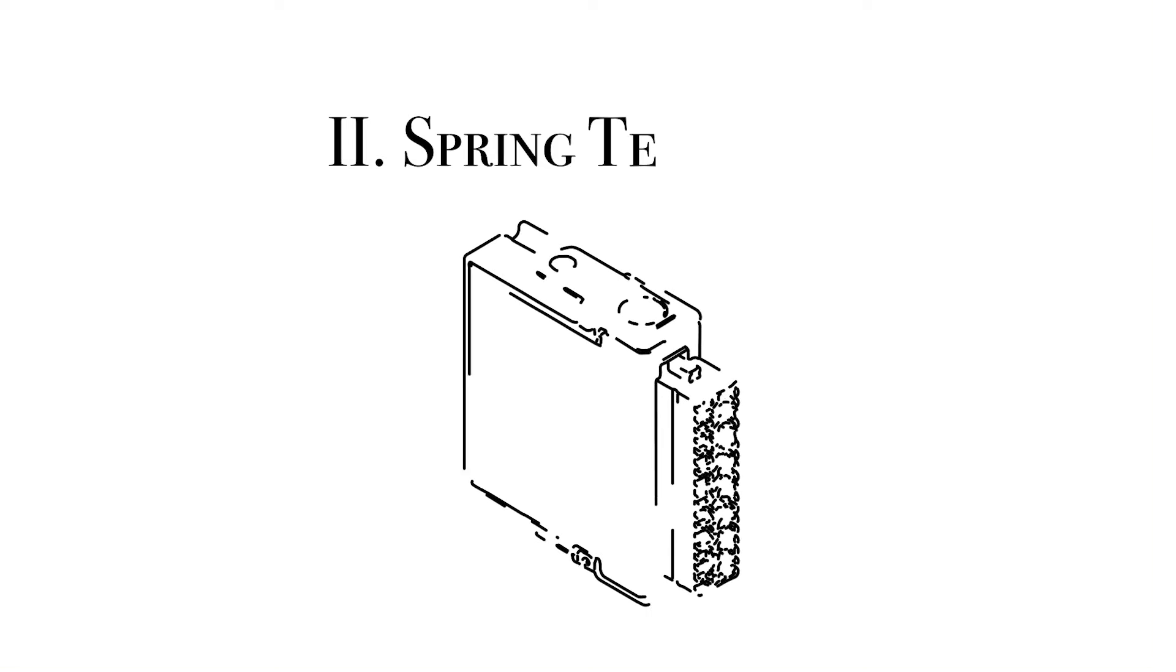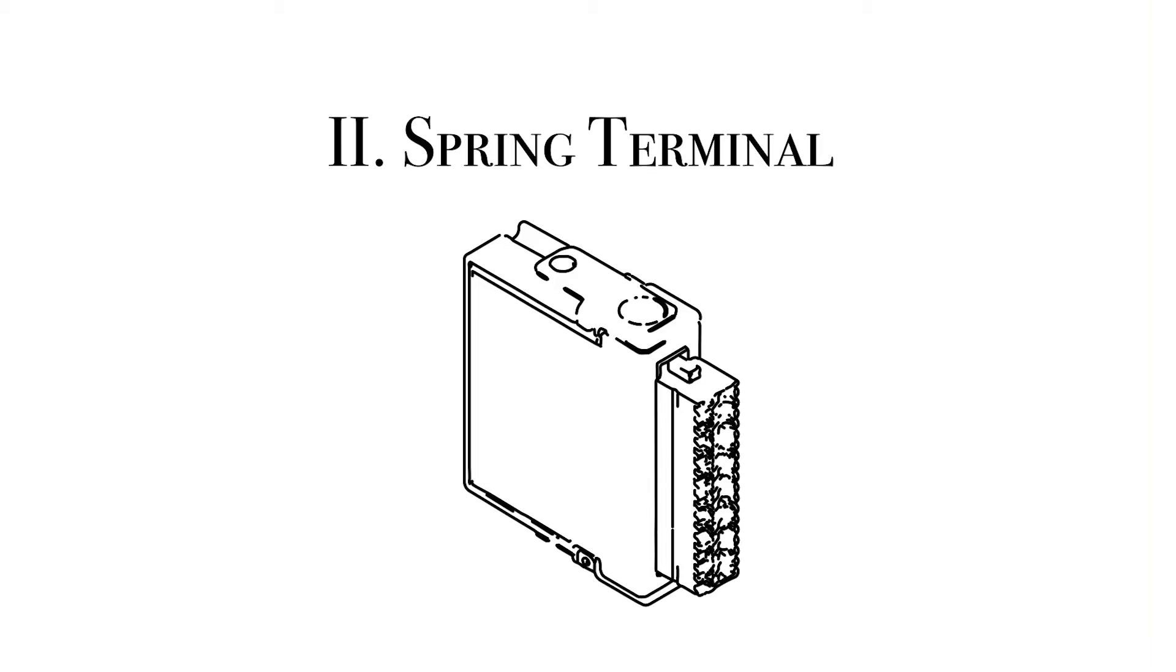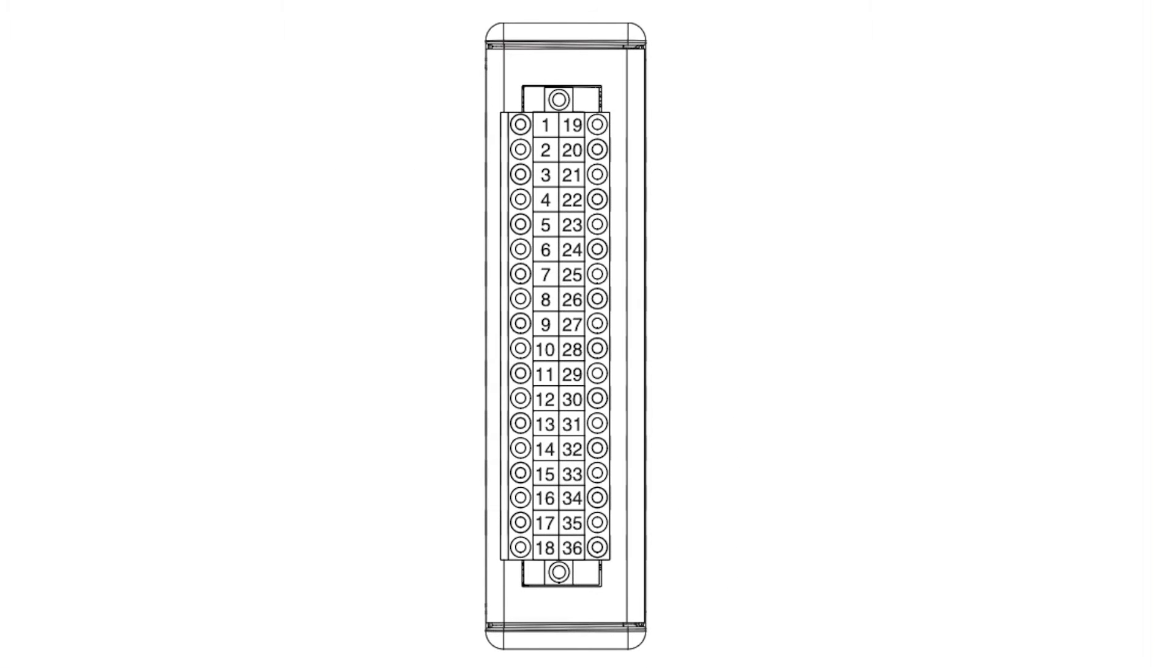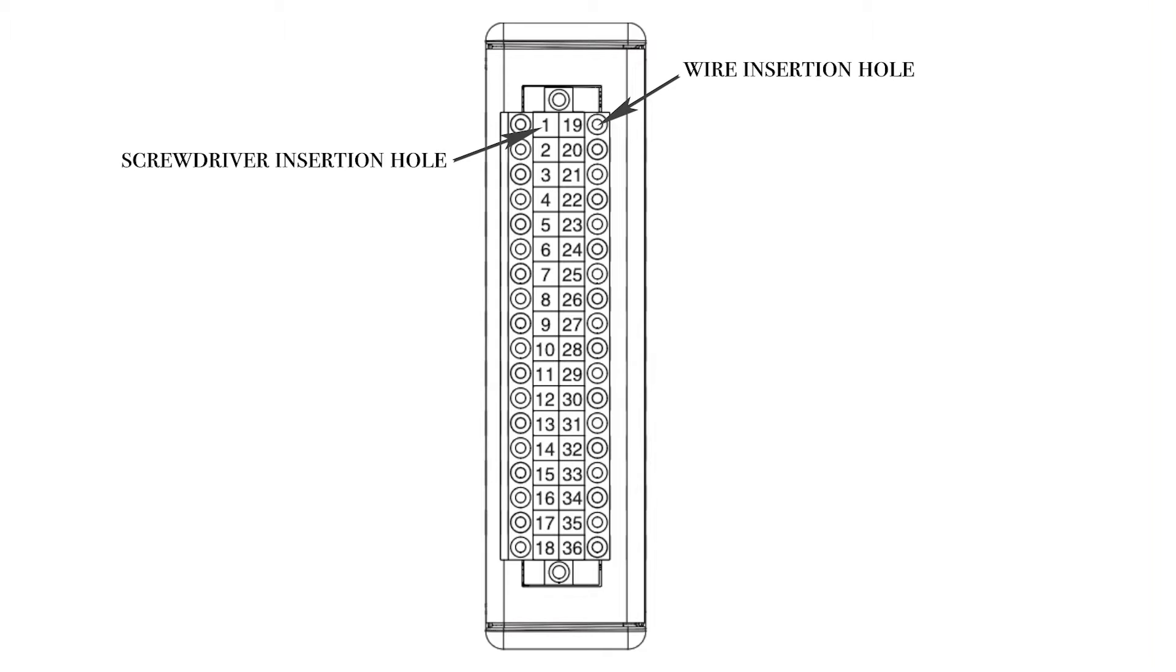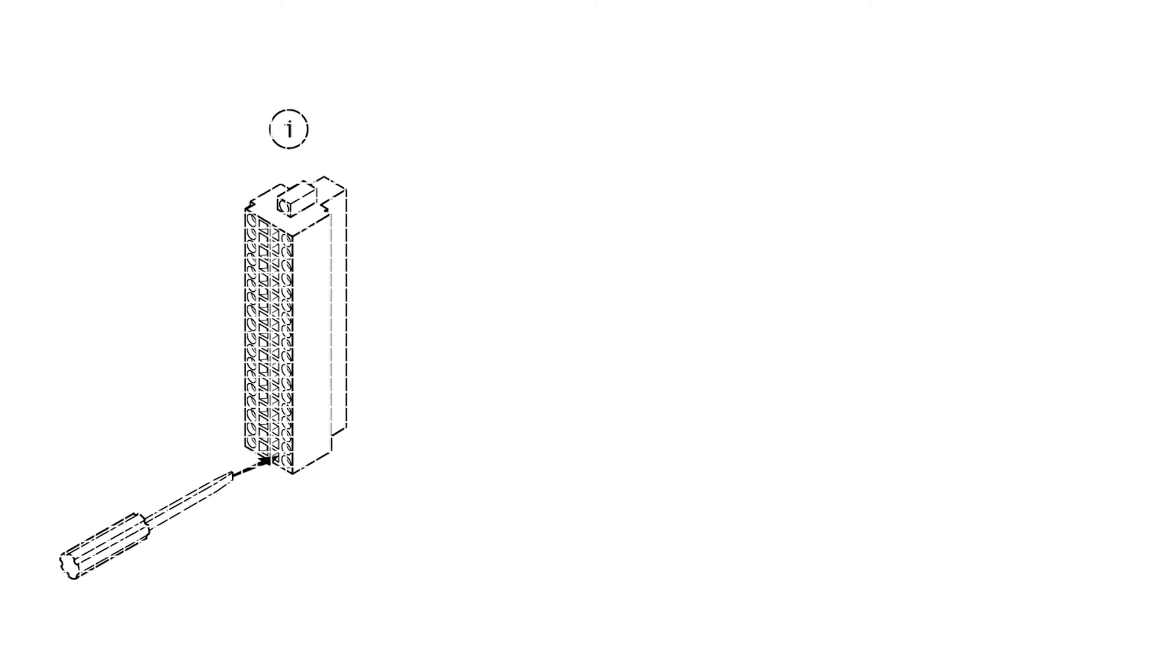The second connector type is the spring terminal. This works in similar fashion to a screw terminal, but instead of tightening a screw to make a connection with a wire, a spring will clamp the wire to the sensor, holding in place much better than a screw terminal due to the tension being automatically adjusted according to the wire gauge. Spring terminals are also better for temperature change, which can cause wires to expand or contract.